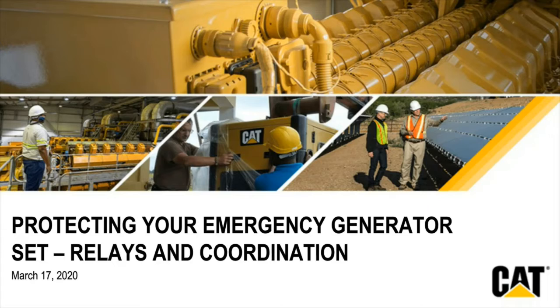As a means of a bit of level setting, I'd like to provide just a little bit of background. Electrical systems commonly use fuses and circuit breakers to protect their electrical equipment. A circuit breaker coordination study is used to analyze the tripping times for the series of overcurrent devices being compared. Generally, that means from the source through the largest branch circuit device. Coordination studies, or in some parts of the world called protection and selectivity analyses, are done to determine proper coordination of overcurrent protection devices. Lack of coordination between overcurrent devices can result in upstream devices opening and needlessly interrupting power in other parts of the electrical distribution system.